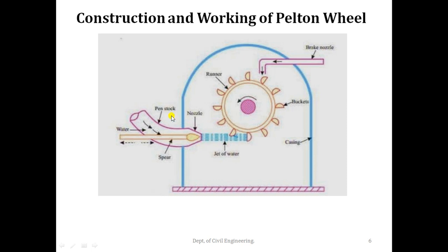Because of the nozzle, all the potential energy is converted into kinetic energy just before the jet hits the buckets of the turbine. The pressure all over the wheel is constant and equal to atmospheric pressure, so the energy transferred to the wheel is due to impulse action. Hence, this turbine is known as an impulse turbine.